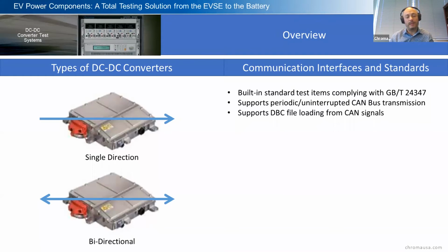In some cases, they could be just static, where they take voltage and have an output voltage, and we make sure it's within specifications, that's it. In other cases, some manufacturers like to program their DC to DC converters, so it's still a universal input and you can program different outputs while staying at the same power level. Or in some cases, the DC to DC converter needs to send status back to the OBC, so it could have CAN communication, automotive Ethernet, I2C, etc. So we have the ability to test through all those parameters and standards.